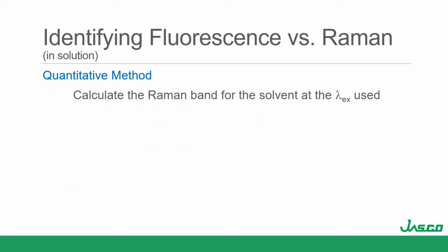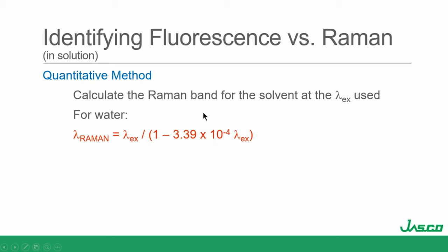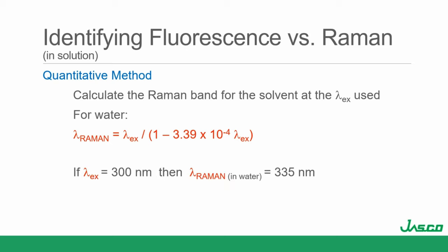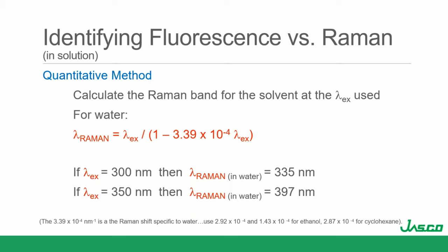Quantitatively, we can calculate the Raman band for the solvent at the excitation wavelength used. For water, it's this equation — you can use it for other solvents by substituting in the Raman shift constant for that solvent. If we excite at 300 nanometers, the Raman band should show up at 335 nm. If we do this at 350 nm, the Raman band will show up at 397 nm.